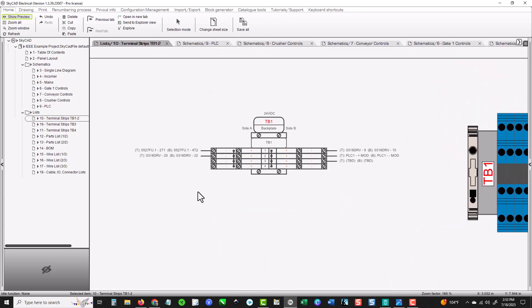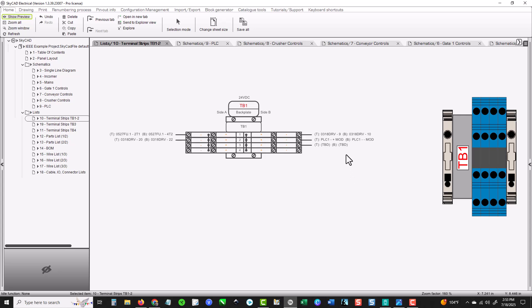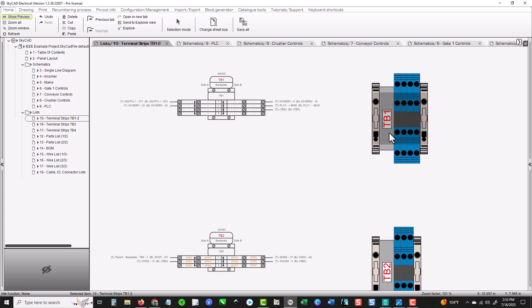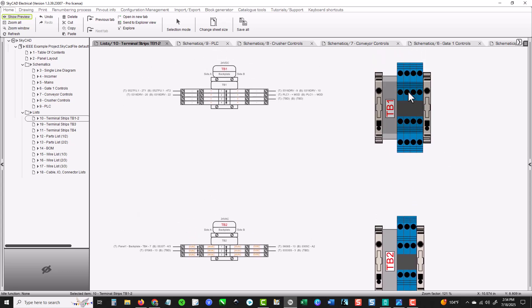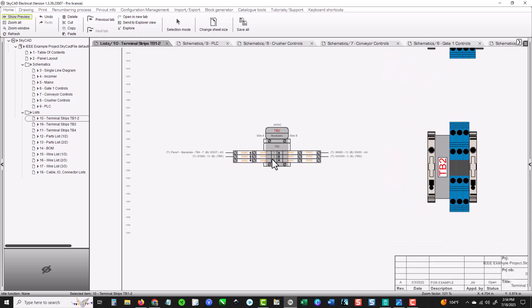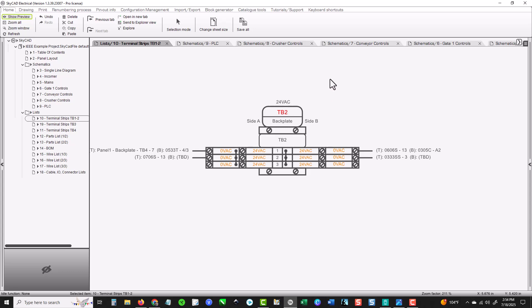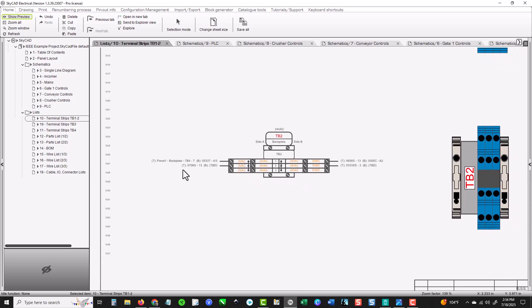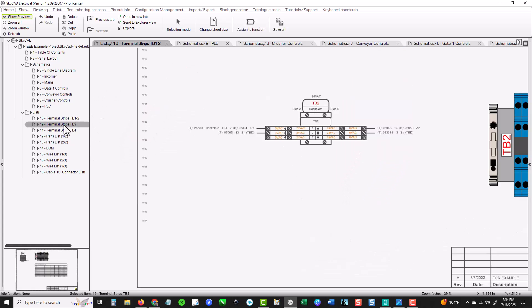You go through all the wiring diagrams of the PLC. Then you've got terminal strips — all the different terminal strips in here tell you where to and from. Generally on the right side it's going out to your field, letting you know where you're going out there, though sometimes it goes within the cabinet itself. Up here, pay attention to the 24-volt DC on that terminal block. These are called end stops — they hold everything together. When you see terminals stacked up like this, this is a stacked terminal block.